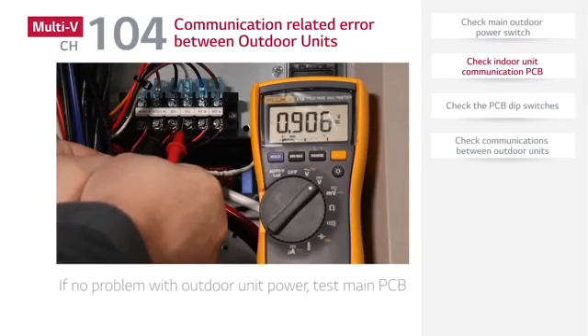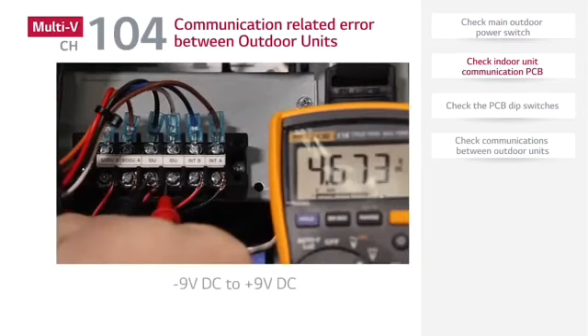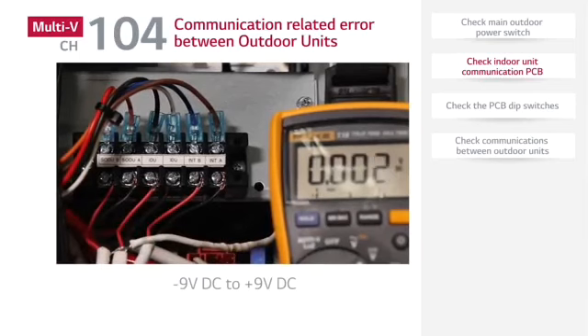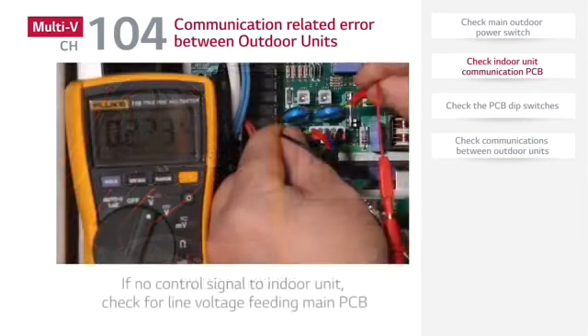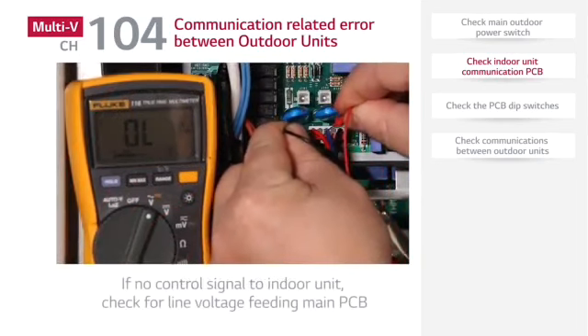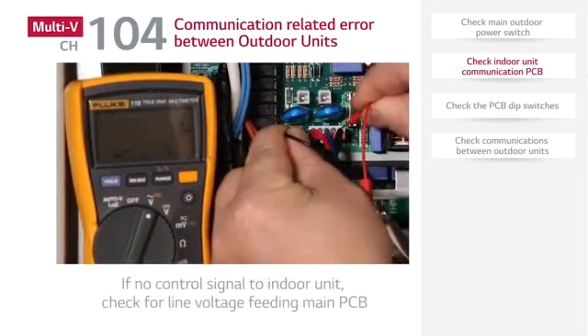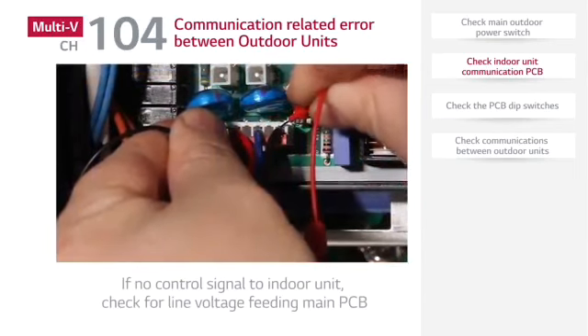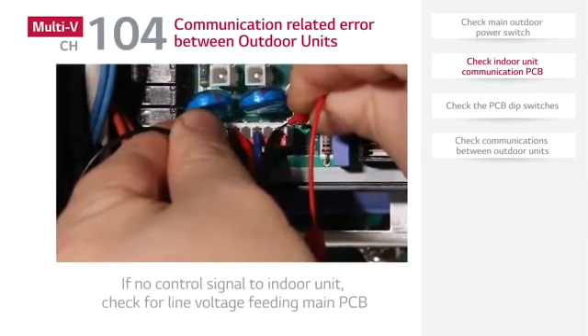First, check the communication signal to the indoor units. The normal voltage value for the communication signal should vary from minus 9 volts DC to plus 9 volts DC. If there is no communication signal to the indoor units, check for line voltage feeding the main PCB. If there is no incoming power to the main PCB, inspect the filter PCB.